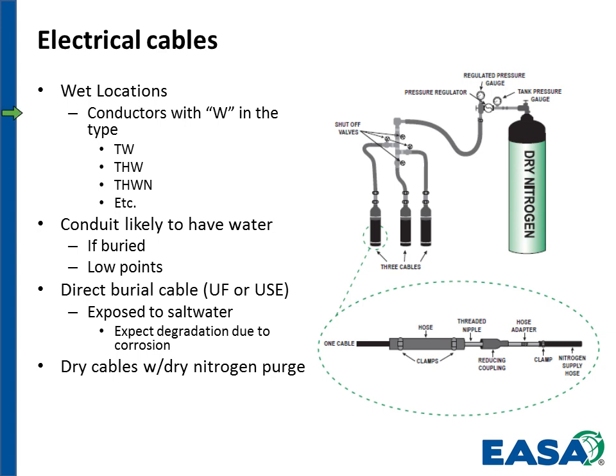Well, as it turns out, the people who manufacture cables are way ahead of us. Any cable that's suitable for wet locations, underground conduit, that sort of stuff, direct burial, are going to have the W in the type. So a TW, THW, THWN, etc. If it has a W in the type, it's suitable for use in a wet location. So you're probably okay.